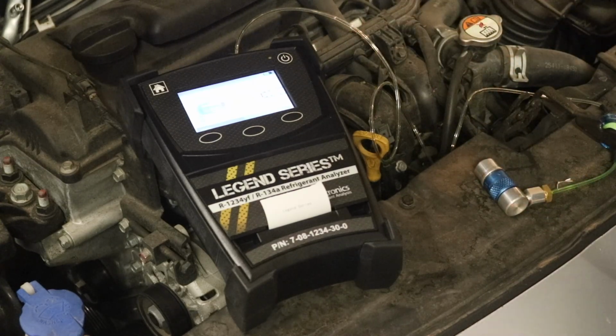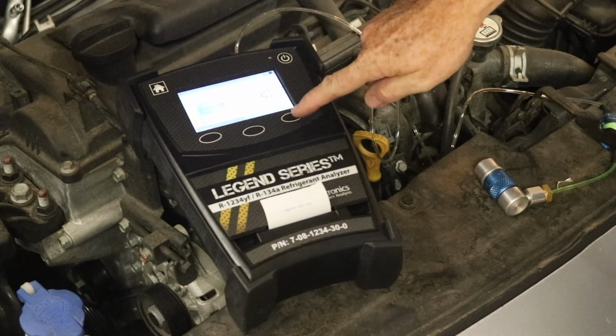Now when I go to display the results, we will see a table that will give us a breakdown of the refrigerant makeup of this system. Also, it will give us a background colour that will indicate at a quick glance how pure that refrigerant sample has tested to be. So if we have mostly R134A with perhaps a little bit of air, we will get a green background because that is generally considered a safe charge for the operator or the technician. As that charge gets more contaminated, or indeed has elements of flammability detected, the background of the screen will change to orange and red. So it's a very quick visual indicator that there should be cause for concern without even having to study the breakdown of the table. So let's press results and we'll see what we can find.